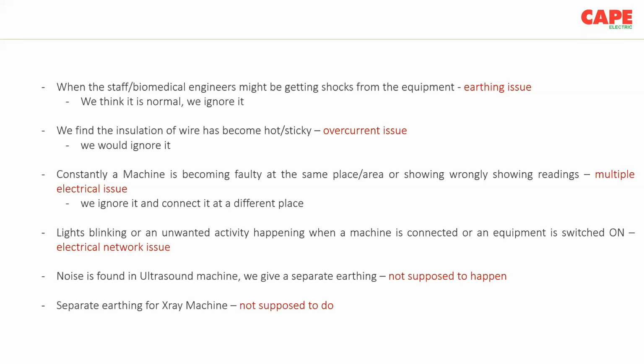Then there would be some unwanted activities happening when equipment is connected. Maybe if we connect a cautery machine, the OT lights would blink, or some other equipment might show blinking or switch off. Even in an ultrasound machine, some noise can be found. We'll think it is due to earthing. It is not supposed to happen, because we are connecting a 3-pin cord to the plug socket. So if earthing is not proper, all of these things will happen.